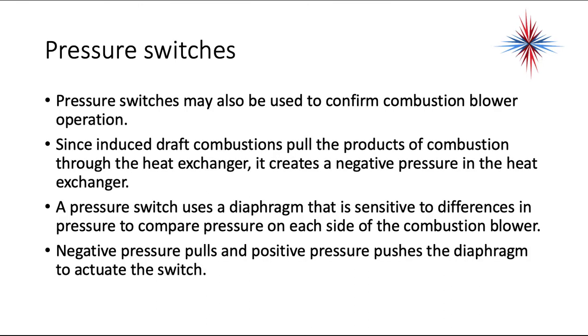Pressure switches may also be used to confirm combustion blower motor operation. Since induced draft combustion pulls the products of combustion through the heat exchanger, it creates a negative pressure in the heat exchanger. A pressure switch uses a diaphragm that is sensitive to differences in pressure to compare the pressure on each side of the combustion blower. Negative pressure pulls and positive pressure pushes the diaphragm to actuate the switch.